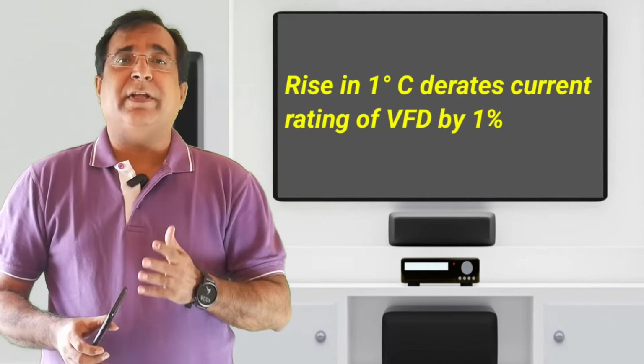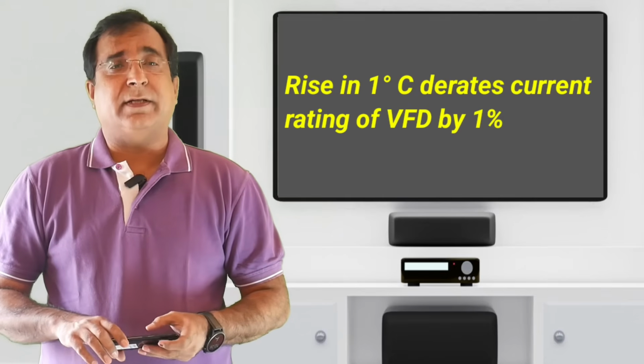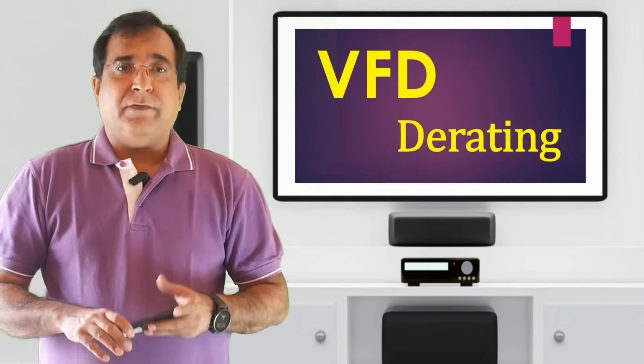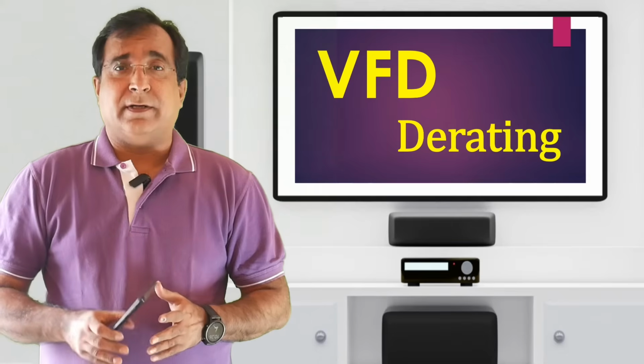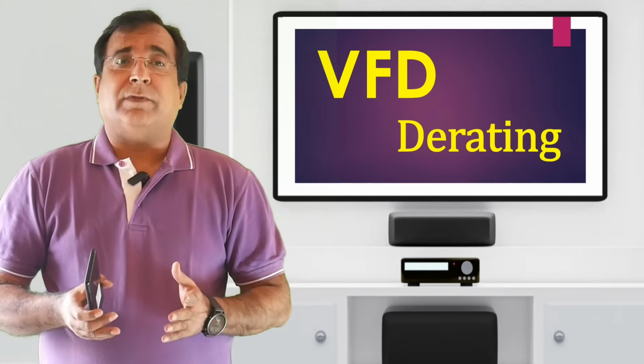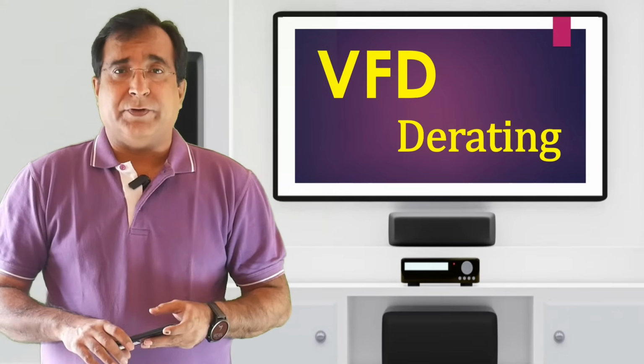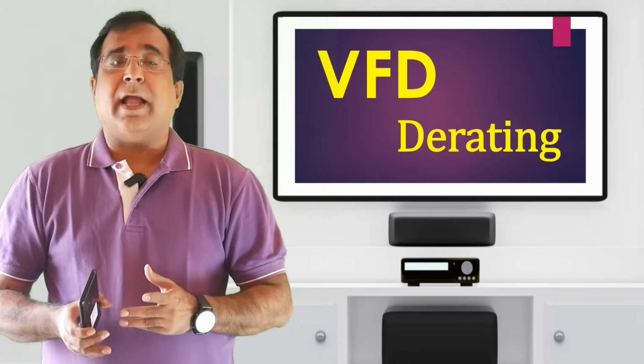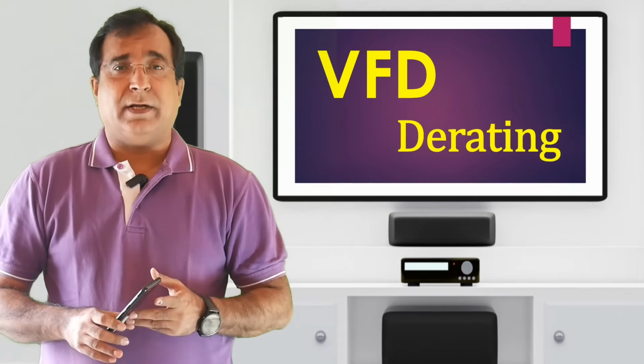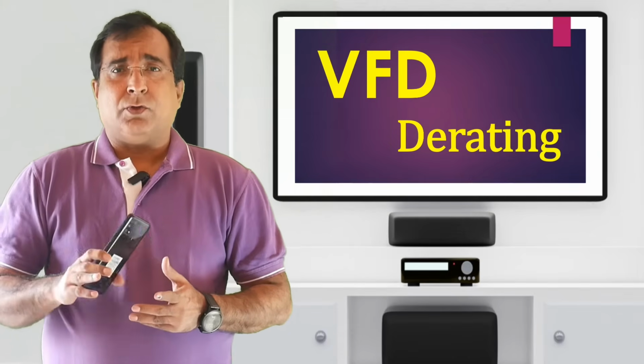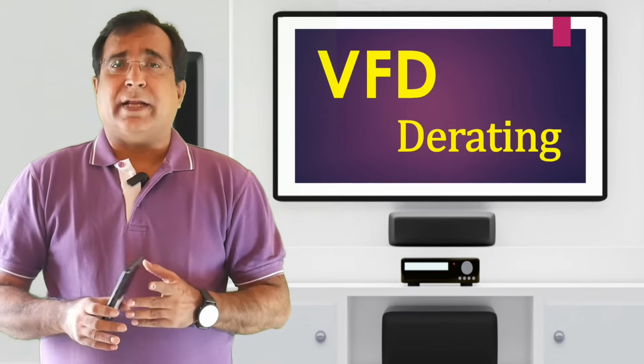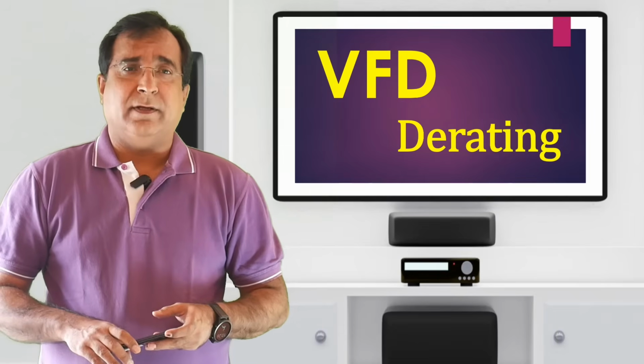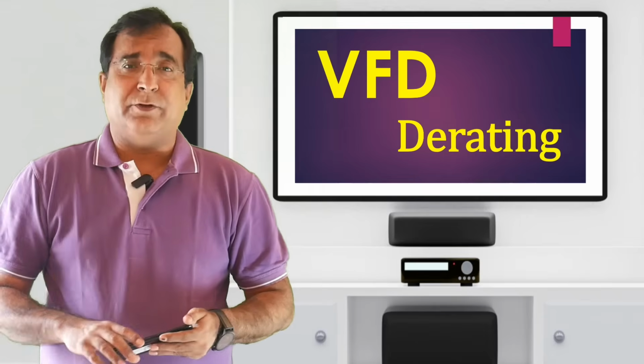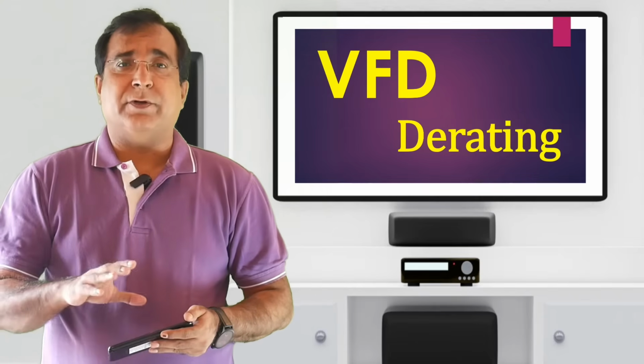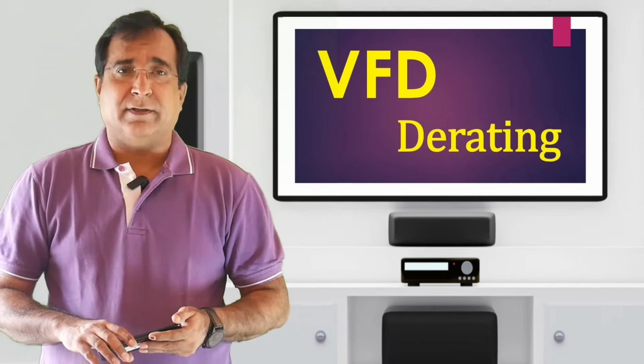For this reason, VFD manufacturers design VFDs for 3300 feet. If the installation is above 3300 feet, then a general rule of thumb is that the VFD current rating is reduced by 3% for every 1000 feet above 3300 feet. So this should be kept in mind while designing a project or selecting a VFD. If you refer to the VFD user manual, you will find the altitude current chart for its derating factor.